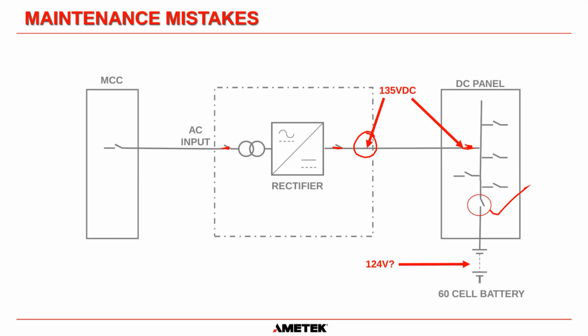So if you measured at the charger and said, okay, 135 volts, my battery's being charged okay, you're not getting the full facts, because if you go out to the battery, if this has been left off charge for a considerable amount of time, it could be 124 volts, it could be even lower, because you didn't know that this breaker here was open. So when you are measuring the voltage for your battery, always do it at the main positive and the main negative of the battery. It's the only place you should be doing it. I know sometimes the battery room is in a different location. It could be downstairs. It could be in a locked room. It doesn't matter. You have to test the voltage at the battery to make sure that the charge is getting there.